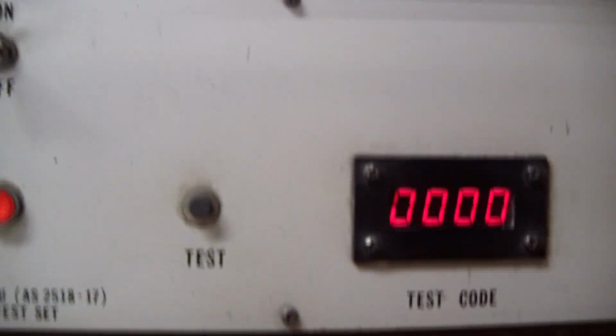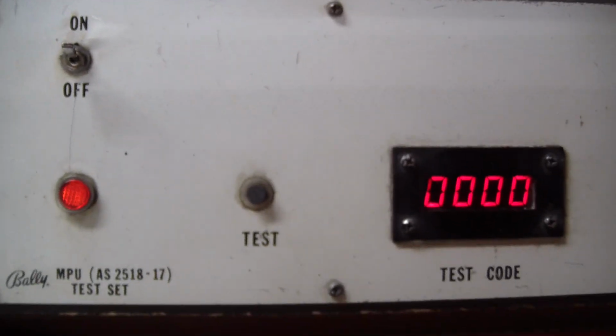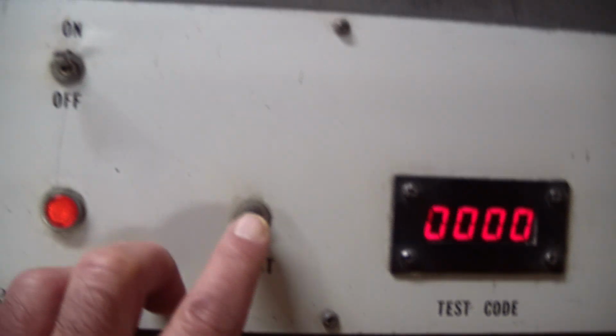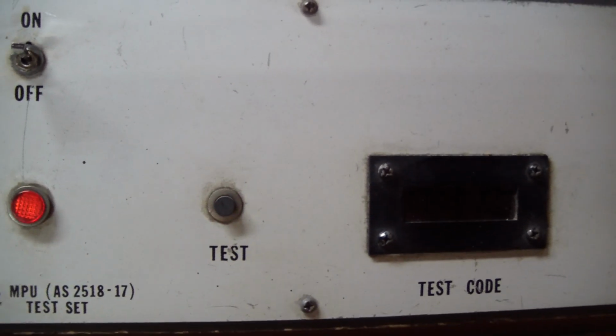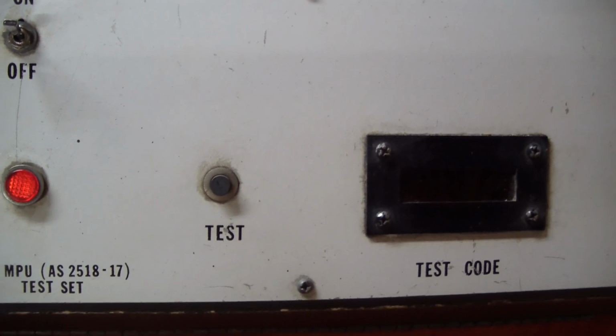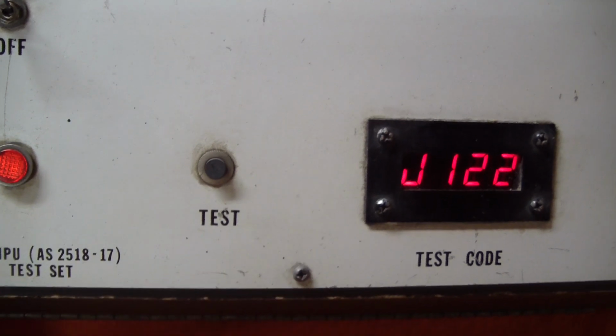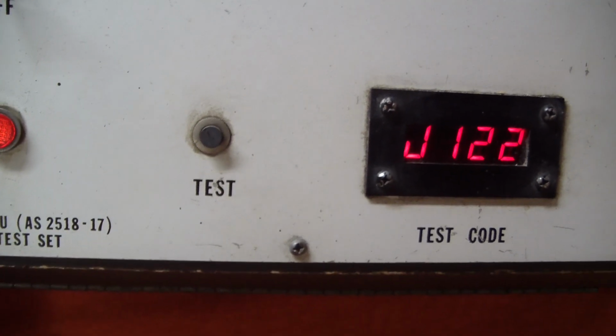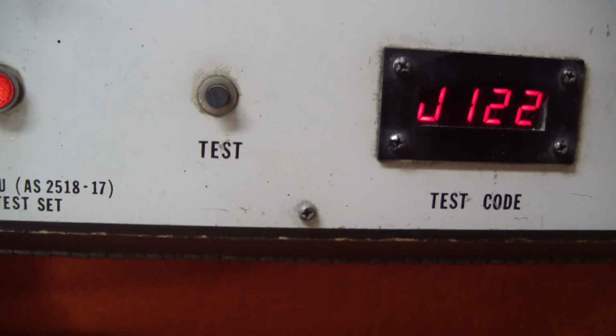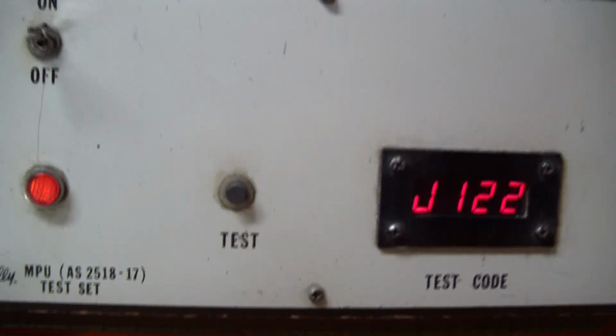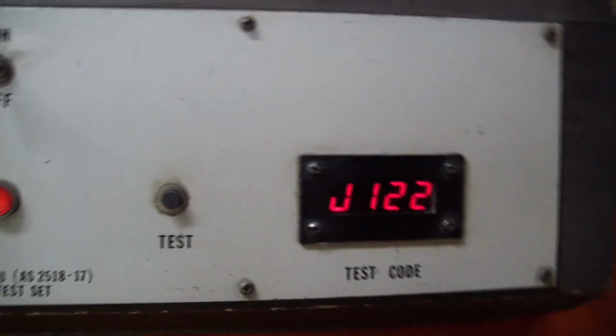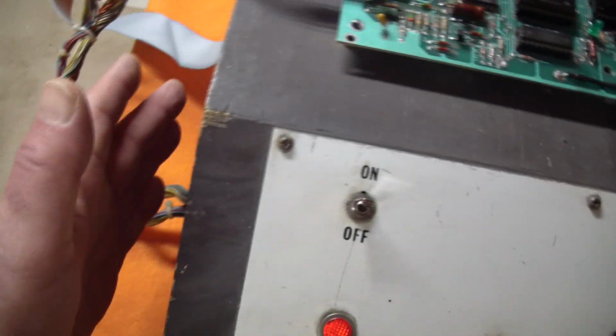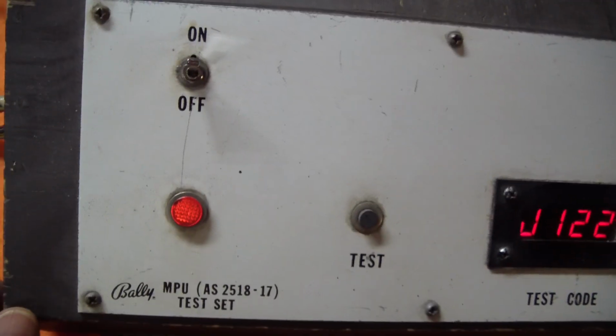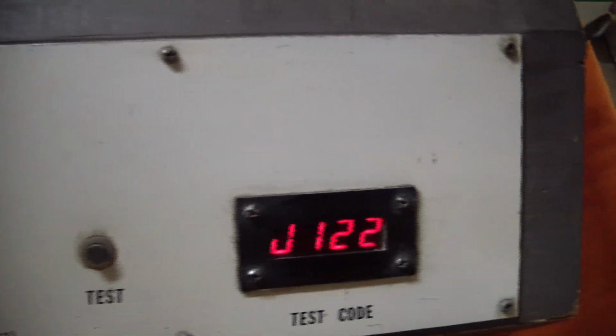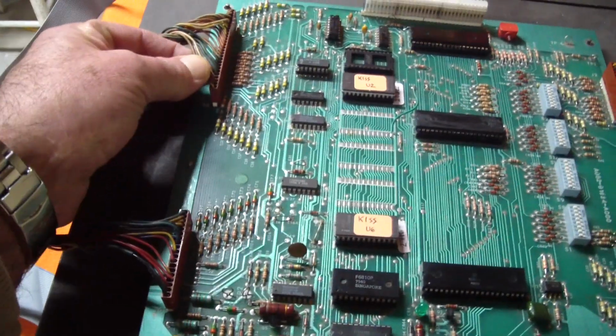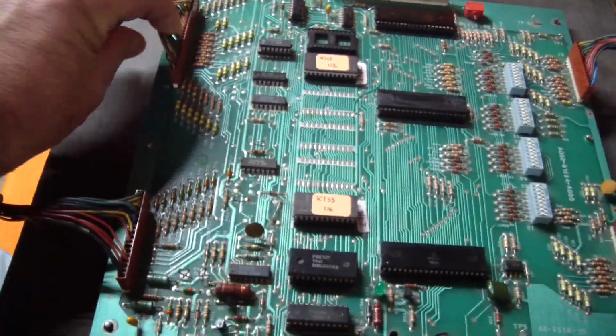So we're back at the 0 here, and we'll start the test. There's our 2 — now look at that. It's giving us the exact same error code on a different machine. So I think it's pretty reasonable to assume that something inside the box is not working correctly, or I'd have to look at the connector, at the wire at pin 22.